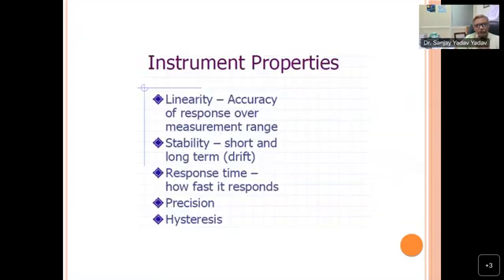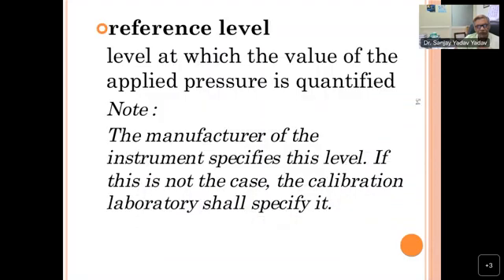Then instrument properties. There are several properties: linearity of the instrument, stability, short-term stability and long-term stability, and response time, basically in precision digital transducers. Then we need precision and hysteresis of the equipment, for all mechanical equipment. Reference level: when you are calibrating two pressure equipment, you need to correct the reference level of both instruments.